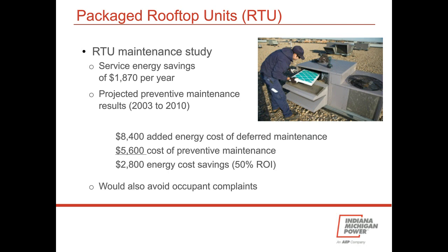effective. So lessons learned, basically that comprehensive preventive maintenance performed twice a year for an RTU serving a retail mall would have paid for itself, along with a 50% ROI over a 15-year life cycle. So the preventive maintenance costs over 7 years of the life, if they had done it, would have totaled about $5,600 as shown here. And by deferring maintenance, though, assuming straight line depreciation and performance, the added energy costs would have been $8,400 over those 7 years, and would have added up to $15,000 over 12 years, and a decrease in the rooftop life of about 3 years if nothing had ever been done.